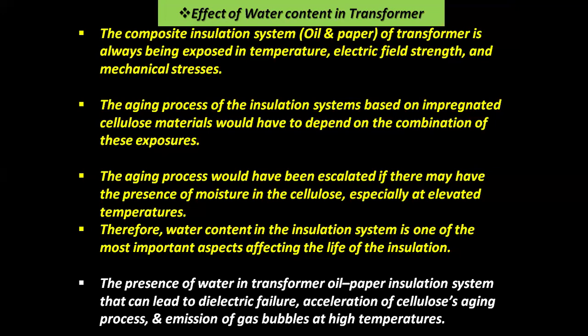The aging process is escalated by the presence of moisture in the cellulose, especially at elevated temperatures. Therefore, water content in the insulation system is one of the most important aspects affecting the life of the insulation. The presence of water in the transformer oil-paper insulation system can lead to dielectric failure, acceleration of cellulose's aging process, and emission of gas bubbles at high temperatures.